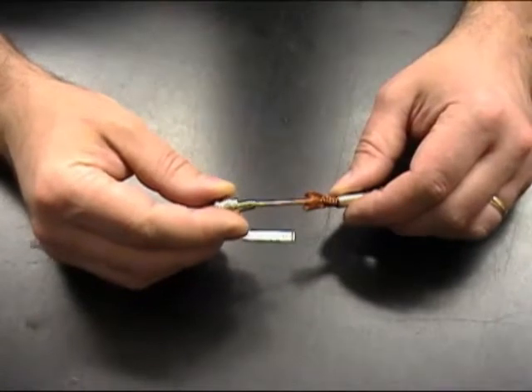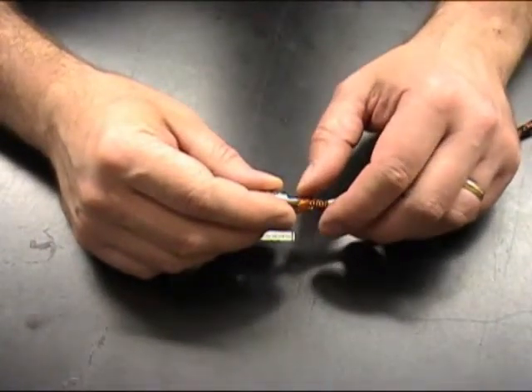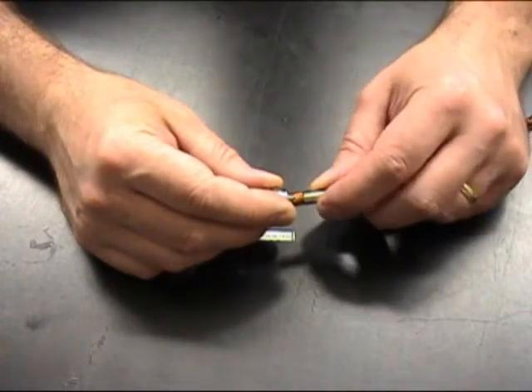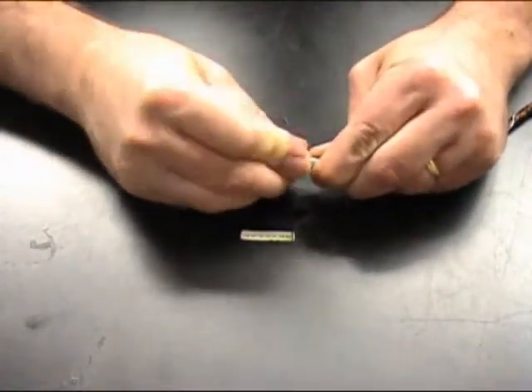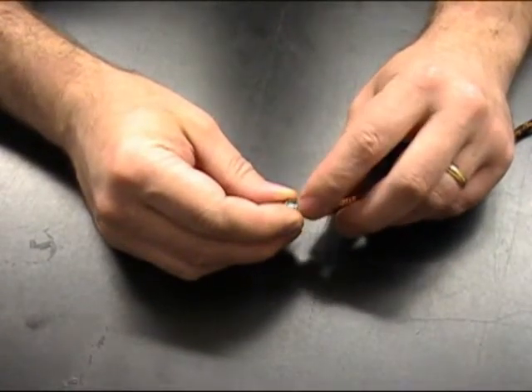Now we're going to slide on the plug body so that the back part of the crimp area just is underneath the braid wire. Then slide up your crimp ferrule so that it just laps the back part of the connector, then push the plug body into the crimp ferrule until the back shoulder of the plug body is snug to the crimp ferrule.